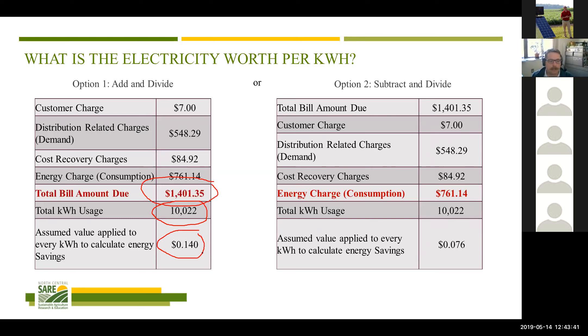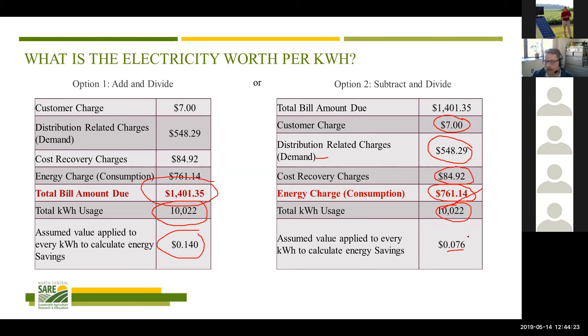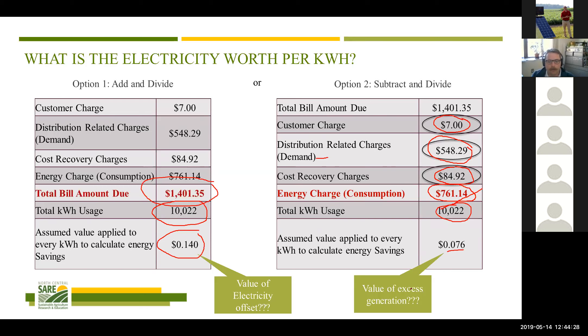But what I generate is not going to be worth $0.14, because there are costs I have to pay regardless. I have to pay the $7 fixed charge no matter what. Because demand is based on how much kW I pull and my solar may or may not influence that, I probably have to pay $548 for my demand fee and also $84 — I cannot offset those with solar. I can only offset the energy portion: $761 divided by 10,000 kWh gives me $0.076. So the value of my energy offset is more like 7.6 cents, not 14 cents.